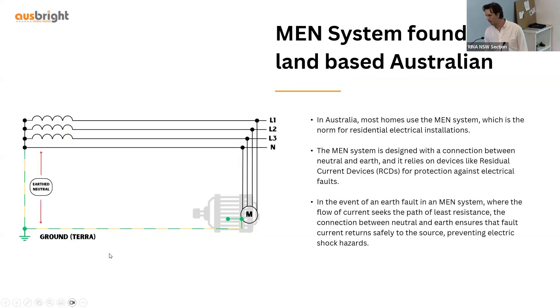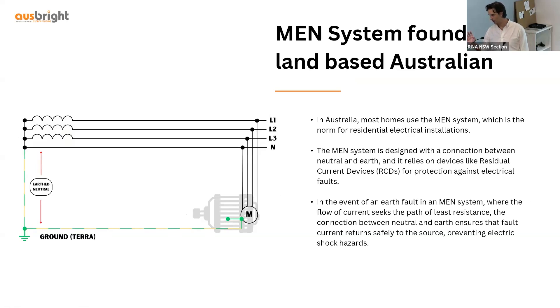This is an MEN system — what you would find in your homes. You have that Earth-neutral connection, which you can see here. Earth is connected to neutral, so in the event of an Earth fault, this Earth would be used as the low impedance path to carry the strong Earth fault currents.